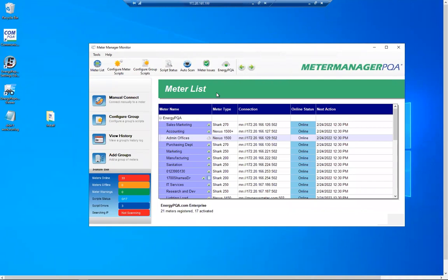If a meter is offline, it will say the meter is offline. It's not able to get into the kind of detail that a technician would be able to, because when a meter goes offline, we can't tell why it's offline. We just know that the meter is not responding. Similarly, with wiring, it can detect that the CTs are out of sequence, but it can't tell why. It can't tell if the voltage is low because the wire is loose versus the entire system being a little low. But it can tell you what the meter sees.